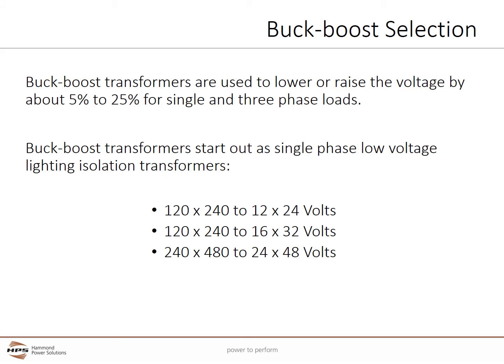Buck boost transformers are used to lower or raise the voltage by about 5% to 25% for single and three-phase loads. Buck boost transformers start out as single phase low voltage lighting isolation transformers in three different voltage combinations.